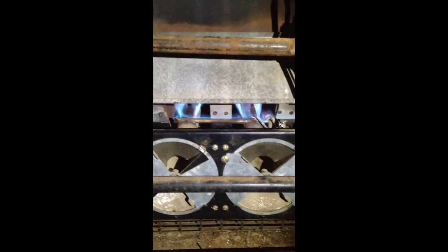Here we're looking at a furnace with a cracked heat exchanger. You can see right now the three burners — they all look pretty uniform, pretty good flame spread throughout them. They're actually even pretty dirty and they've got a decent flame. So here's with a little light what we're looking at.